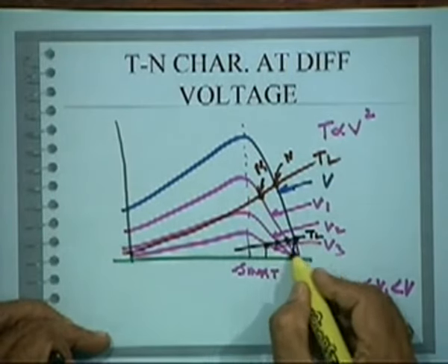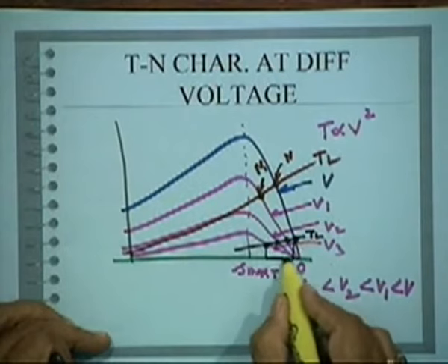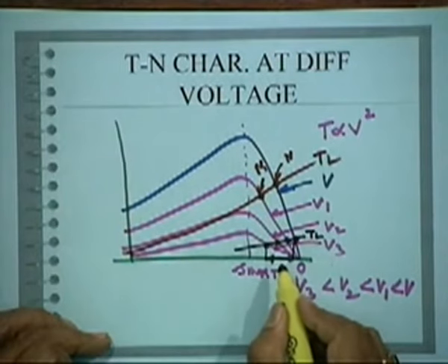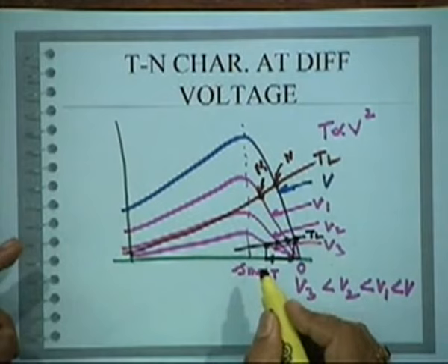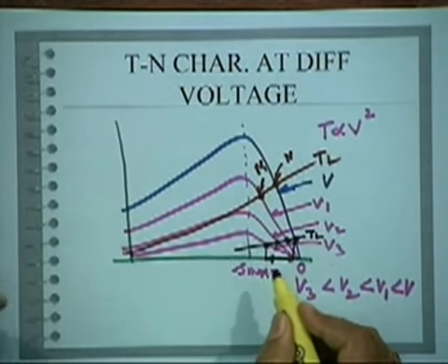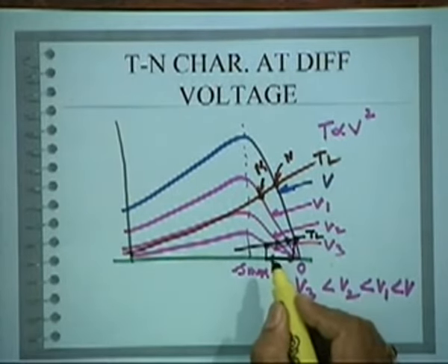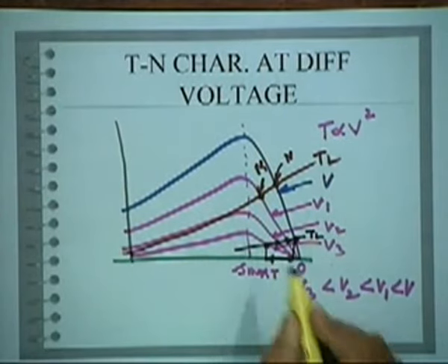Look at what is the range you can have. The range of speed you can have is very small, right. So you cannot have a large range of speed. This is one of the features of speed voltage control, right. You can have very marginal range of speed. Maybe it can be used mostly for energy saving. If it is underloaded, you reduce the voltage so that energy consumption is reduced.